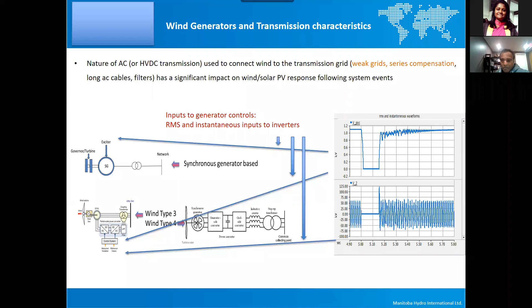It's the cable. These long cables introduce a network resonant, parallel resonant point, generally in the third or fourth harmonic region. So when you go through a transience or disturbance, the voltages and currents have components of that transience, and the PLL output gets modulated. So the controls get into all sorts of oscillatory behavior, and you need filters. You can't have filters in the system because that's costly, so you have to put filters in the control parts. When you put filters in the control parts, it makes the controllers slow and rugged against everything else. So those are the challenges.